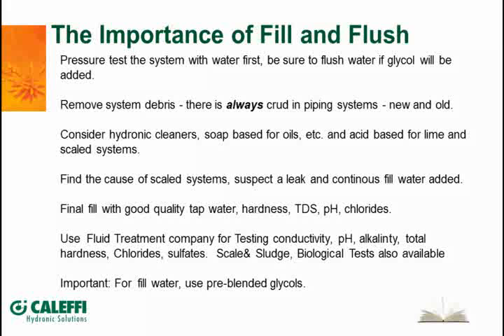In a radiant system, that can be hard to find sometimes. If it's an in-slab system, you might have a pinhole from when you put the tubing in and you've got a small leak, and that small leak takes on maybe only a couple gallons a week or something like that. But over the years and the months, that's going to add up, and that's where you're going to see that hard water being added to the system, clogging up heat exchangers and putting that deposit on. Any deposit that you get on the pipe or on the heat exchange surface is going to limit the amount of heat transfer you can get.